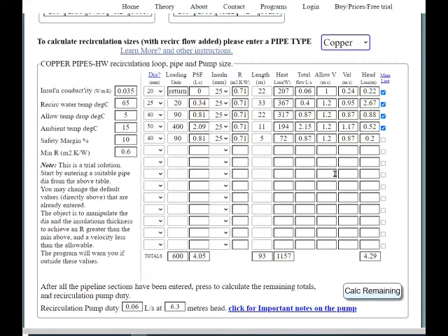Now we can see it's added a few things up. So it's added the total heat. We found the total heat loss is 1,157 watts. See, heat loss in watts. It's 1.1 kilowatts. It's a reasonable amount of heat that you're losing just pumping it around. That's going to cost a lot of money. If you want to save some money, you can make the insulation thicker. So let's try, especially on the bigger one. We'll remember that 1100 here.